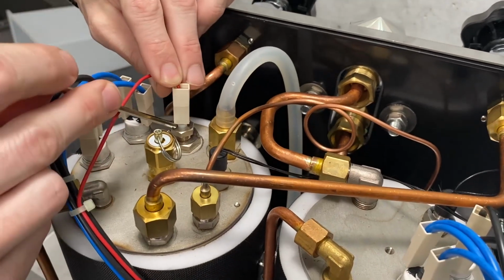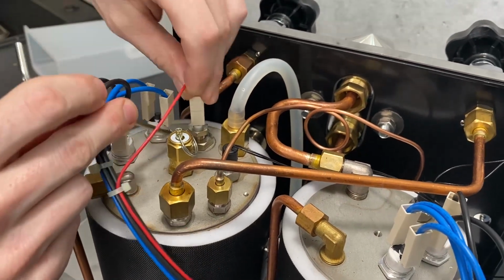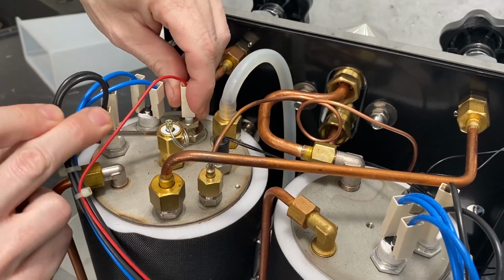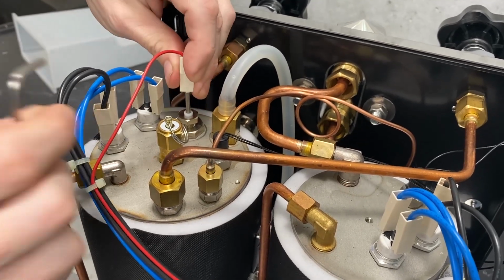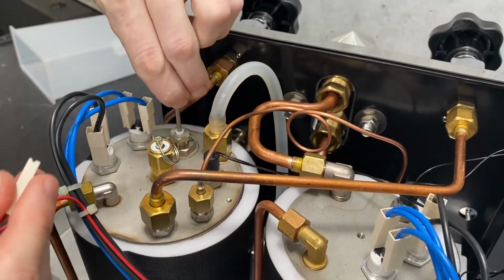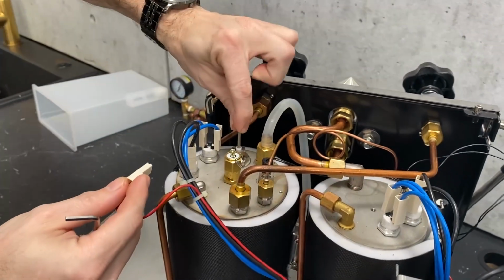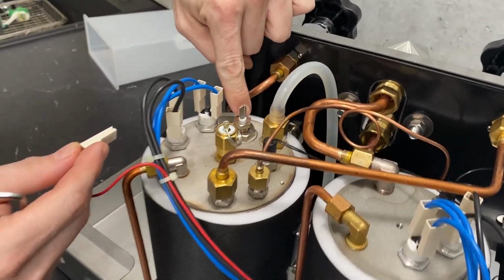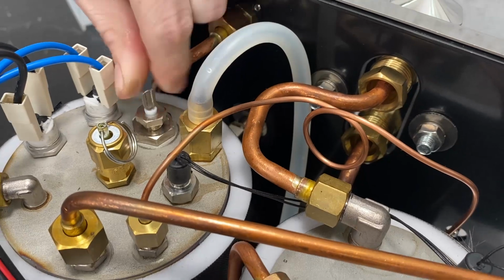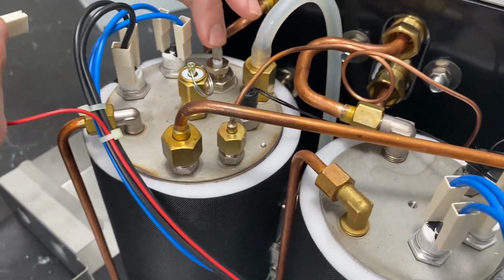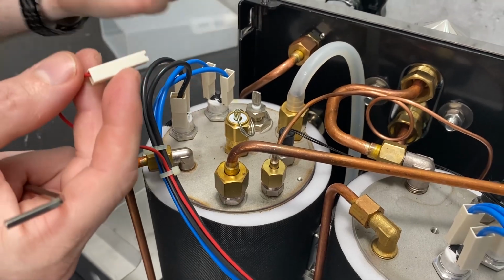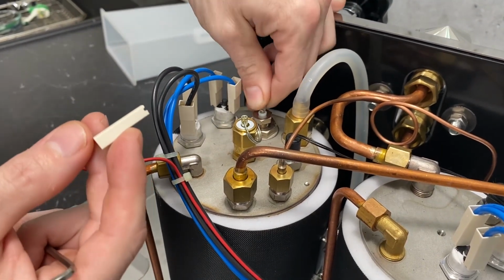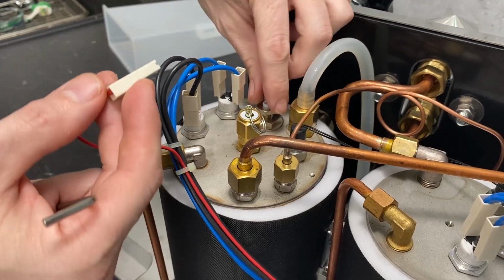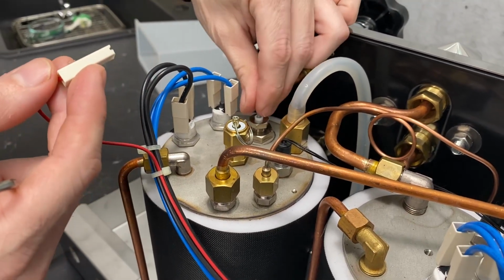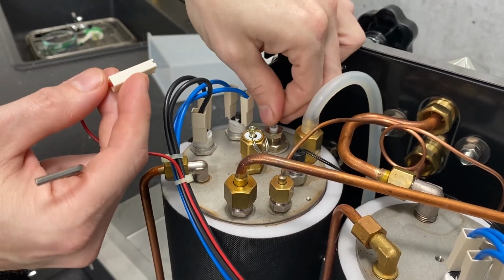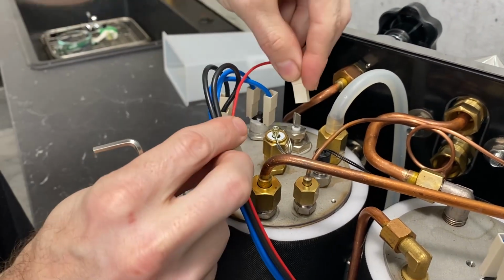Moving up to here, this is your level probe for the liquid level control circuit. This needs to be tightened down. If you ever pull on that cord and this whole thing comes right up like that, tighten down this top bolt. You don't want that to move up and down so easily, because this goes directly into your boiler and is touching water, so with that pressure, if it's moving that easily, you're probably going to end up with a leak in here. I've never seen one be so loose that it flew up or anything, but that's obviously a thing that could happen.